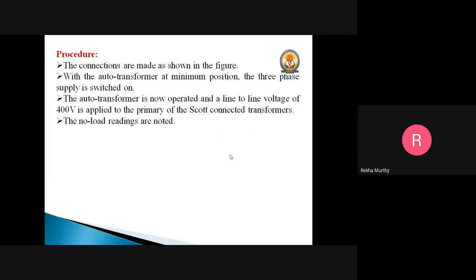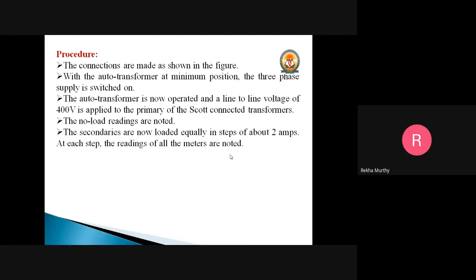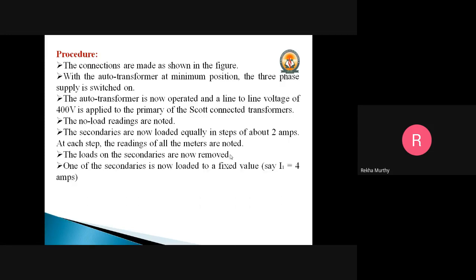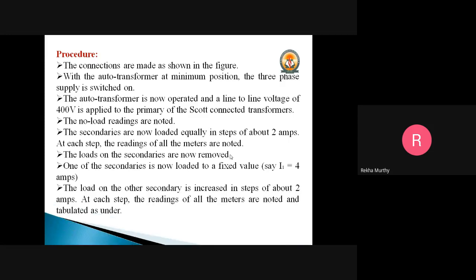Finally, you should not directly switch off the supply. We need to remove the loads on the secondaries and bring everything back to the zero off position. Then minimize the auto transformer to zero - the 3-phase auto transformer we used - bring it to zero position, then switch off the supply. This is the procedure we need to follow to conduct this experiment.